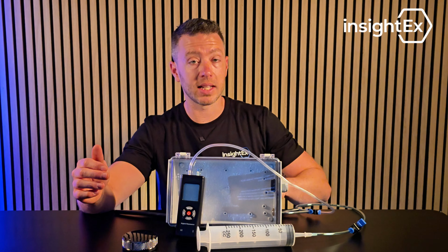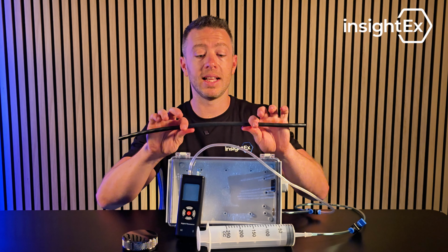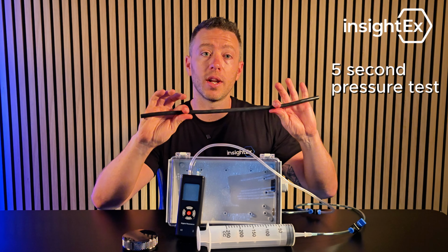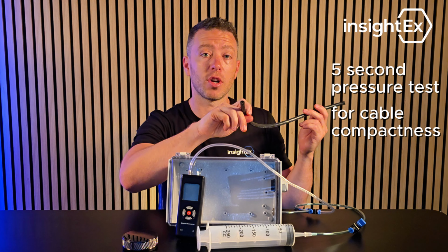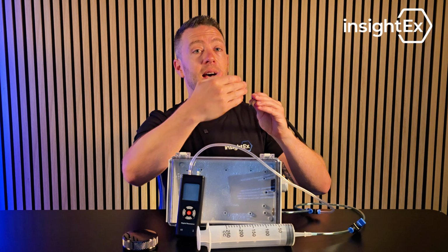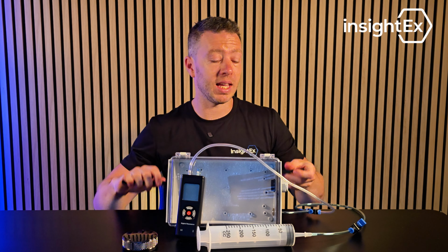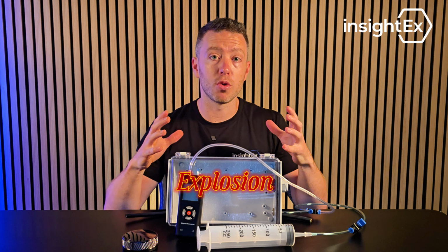Here's how it works. The Annex C test is very straightforward. It's a 5-second pressure test on a cable to check whether it's loosely constructed enough to let a flame pass through the gaps and escape, because in EXD, we're trying to keep that explosion in.